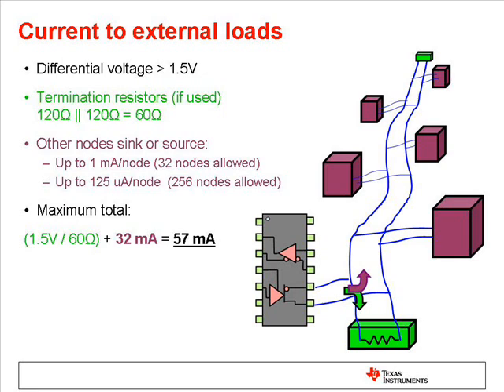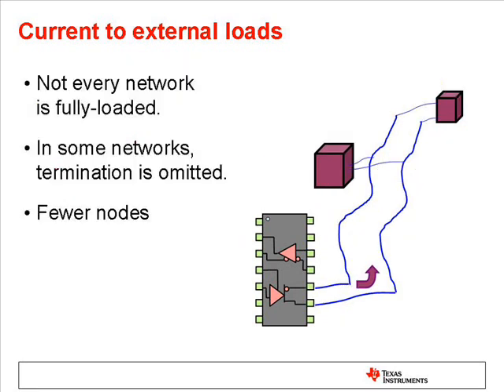For a fully loaded bus with standard parallel termination, the external load current should be less than 60 milliamps. For networks with fewer nodes or with less termination, the load current can be much less.